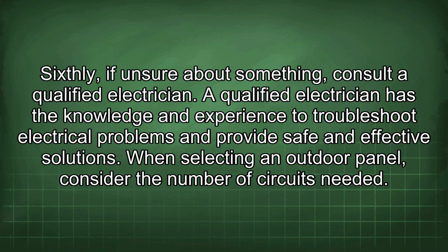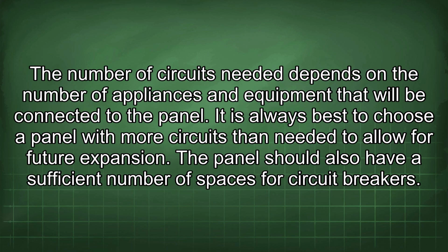When selecting an outdoor panel, consider the number of circuits needed. The number of circuits needed depends on the number of appliances and equipment that will be connected to the panel. It is always best to choose a panel with more circuits than needed to allow for future expansion. The panel should also have a sufficient number of spaces for circuit breakers.